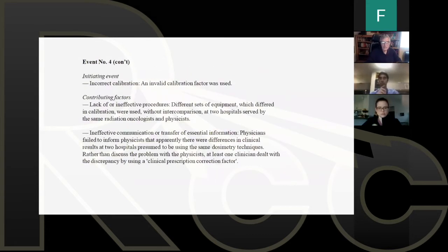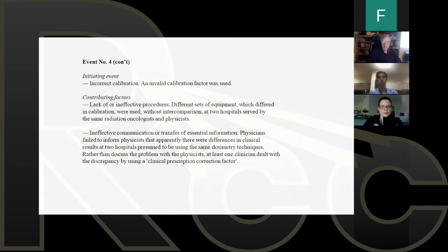An invalid calibration factor was used. That was the initiating event. The contributing factors: lack of effective procedures. Different sets of equipment, which were different in calibration, but without any intercomparison, nobody knew that those systems were different. And of course, communication, always a problem. How do you get essential information down the chain from one group to another? So this resulted in the doctor actually using a clinical prescription fudge factor, calibration factor, to make up for what the doctor was seeing as a change in tumor response between the different centers.